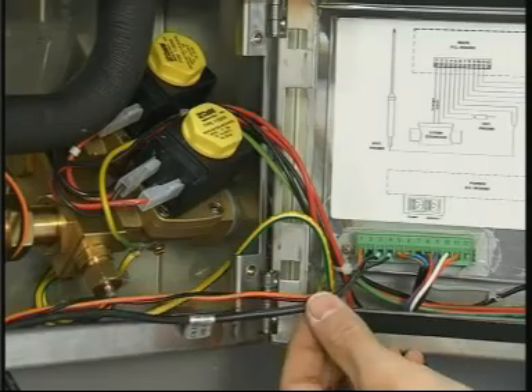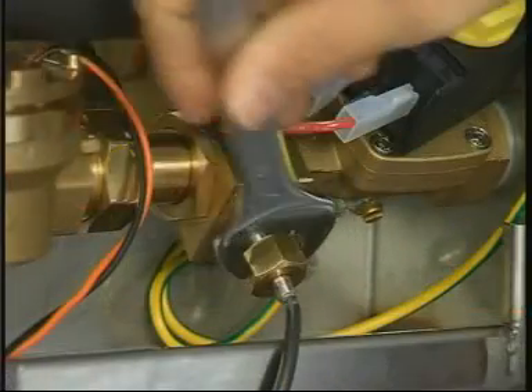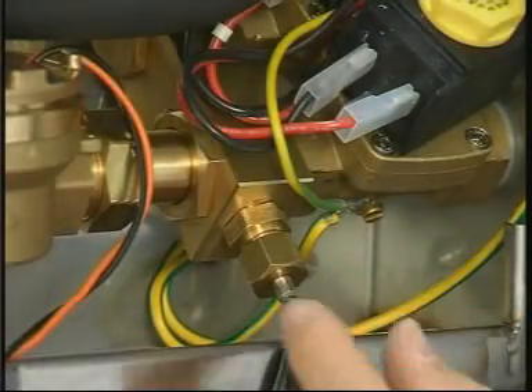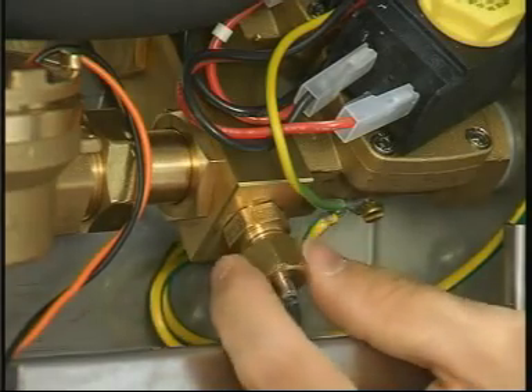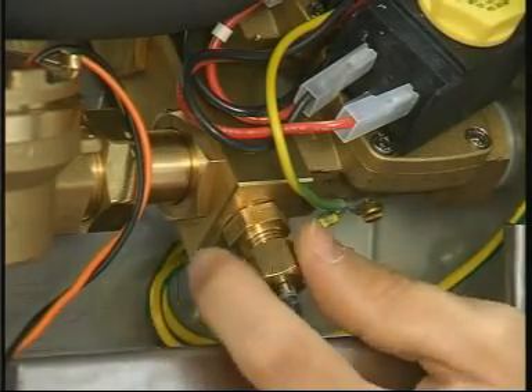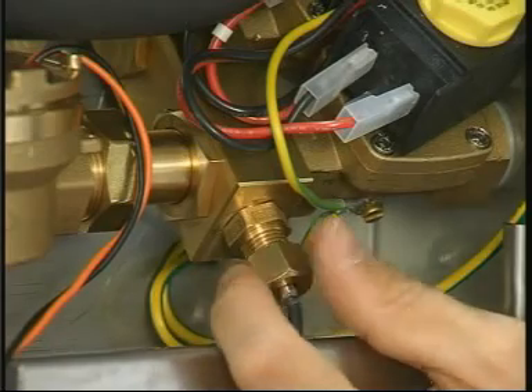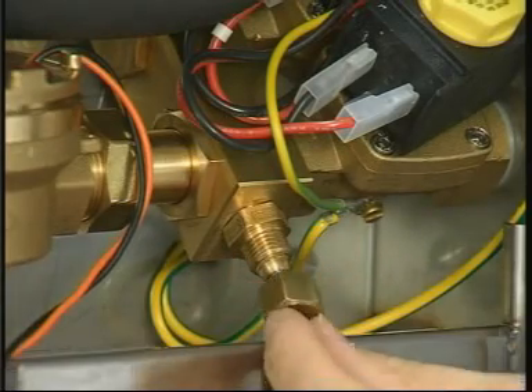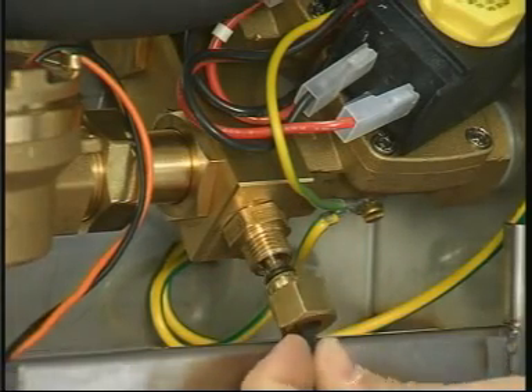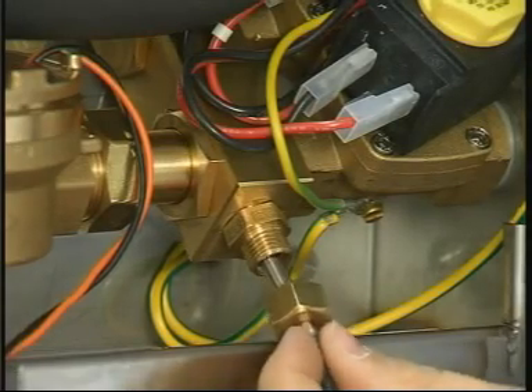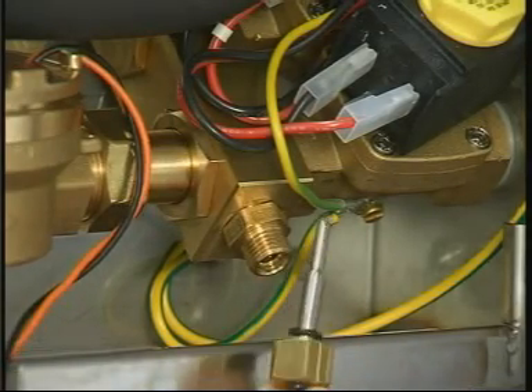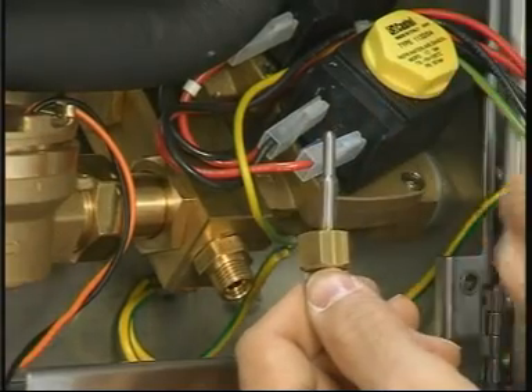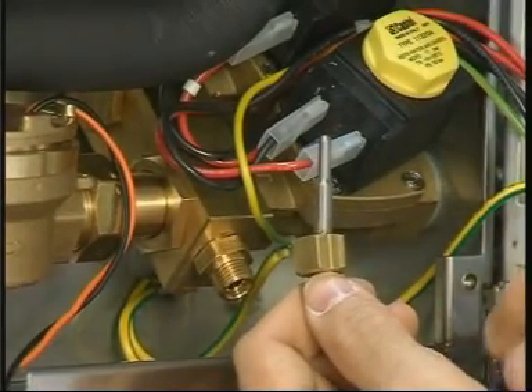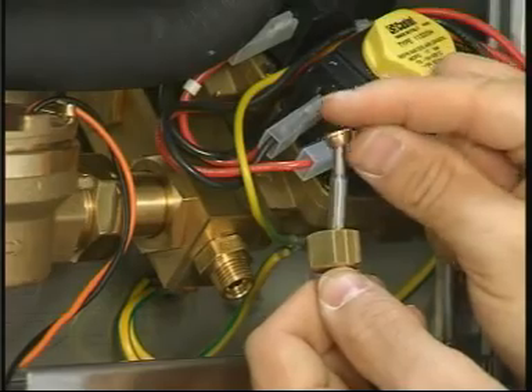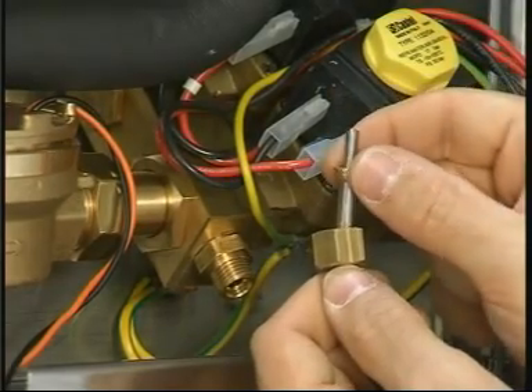Unscrew terminals 3 and 4 as shown. Unscrew with spanner number 15 the tightening nut of the probe and extract the probe. Assemble the replacement probe, paying great attention to the O-ring.